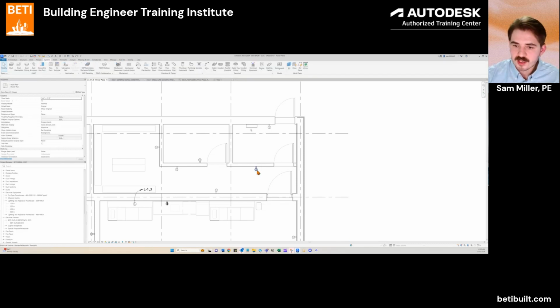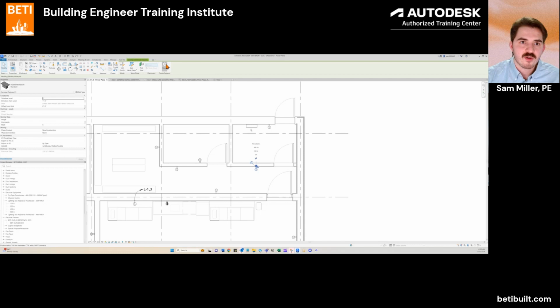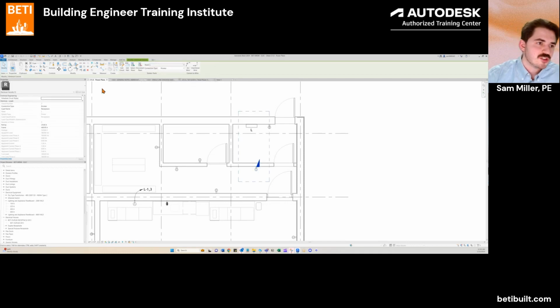I can click here, click Power, and this brings up the properties window, which is actually how I like to edit what's going on in the panel schedule myself. I can see the load name and the circuit breaker rating. Instead of going back to the panel schedule every time, I can change things here - for example, I'll rename this to storage receptacles. If I wanted to change the circuit breaker, which I don't need to here, I could also do that in this window. I'll hit Apply.